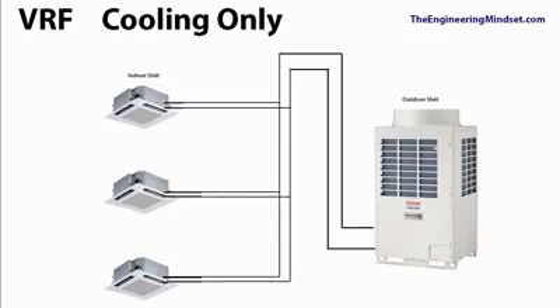So looking at a basic schematic of the cooling only VRF system, you can see here we've got the outdoor unit, and indoor we've got all these cassettes, ceiling cassettes. You're not limited to these, you could put them into AHUs, maybe fan coil units, etc. But for simplicity I'm just going to stick with these. And then notice there's a two-pipe system running around here and off to the outdoor unit. Each indoor unit also only has two pipes, and it joins this common feed flow and return, which supplies and takes away the refrigerant. So these are key components of the system, and as you can see it's very simplistic, and it's just a more advanced version of your basic split AC unit, providing air conditioning to multiple zones.